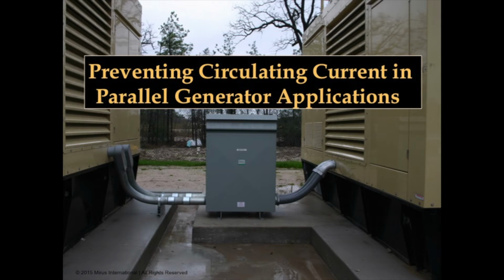Thank you very much, Leah, and good day, everyone. It's great to have this opportunity to speak with so many of you spread out throughout the world. It just goes to show that no matter where we're located, we face many of the same challenges. MIRUS has been assisting customers all over the world in resolving problems related to power system harmonics since our inception in 1991. Our foray into the parallel generator market began when customers approached us for a solution to their high circulating current problem. They asked us because they saw it as a harmonics issue, since the current was 3 times the fundamental frequency, or 180 hertz here in North America, and 150 hertz where the fundamental is 50 hertz, and many other areas in the world.